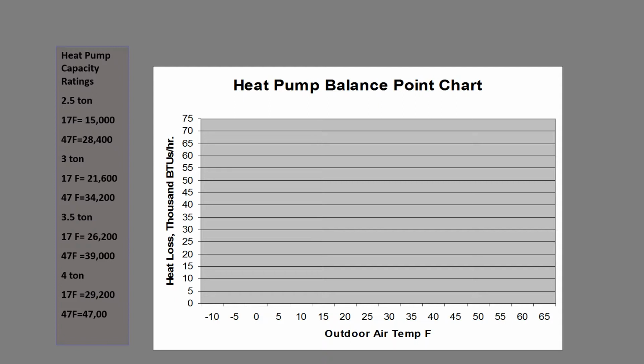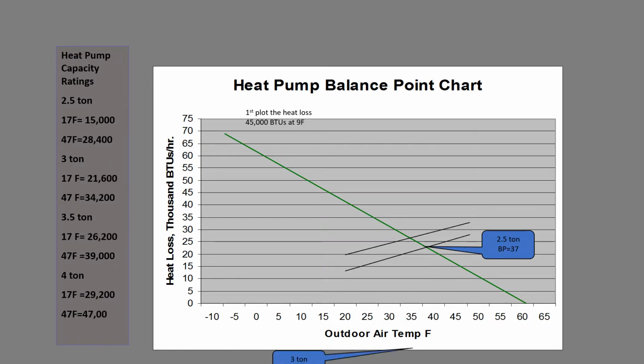So this is how to create a heat pump balance point chart. The first thing that you do is you create the heat loss of this house. You need 1 point to do that. You can take your heat loss at any given outdoor temperature. Usually it's your design temperature, and you anchor it over to 65 degrees. Sure enough, the warmer it is, the less the house needs to maintain temperature. So yeah, this house has a 45,000 BTUs at 9 degrees. Our first one here is a 2.5-ton, and if we just draw a straight line between the 17 and 47 degree AHRI rating points, you get a nice straight line. So the balance point where the two lines cross is 37. Not really a very good fit.